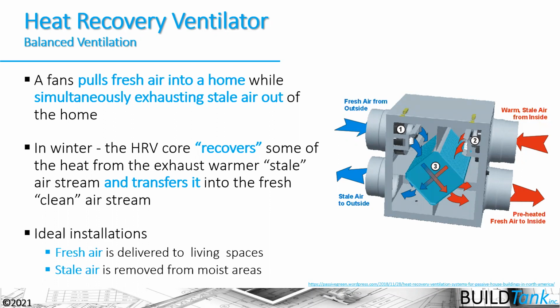So generally what we want is the fresh air to be delivered to the living spaces and the stale air to be removed from moist, polluted areas like bathrooms, kitchens, and laundries there. That's the ideal setup here. That would be an independently ducted heat recovery ventilator. Now, you don't have to independently duct it, but we're not going to go through these other ducting strategies.